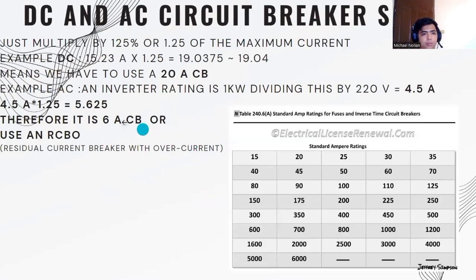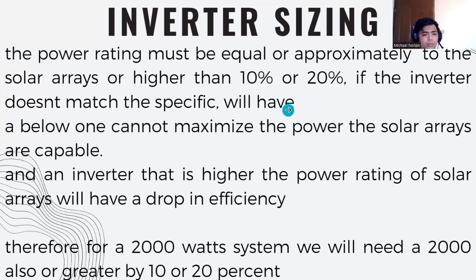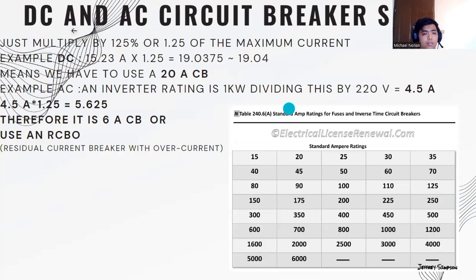Then DC and AC circuit breaker sizing. Wait a sec, did I go past it? I think I went past it. Yes. DC and AC circuit breaker sizing. Let's multiply the maximum current by 1.25. Example, for DC, 15.23 amperes multiplied by 1.25 equals 19.0375, or approximately 19.04. This means we have to use a 20 circuit breaker here. There is no 19, so we just use 20. Not 15, that is too far off.